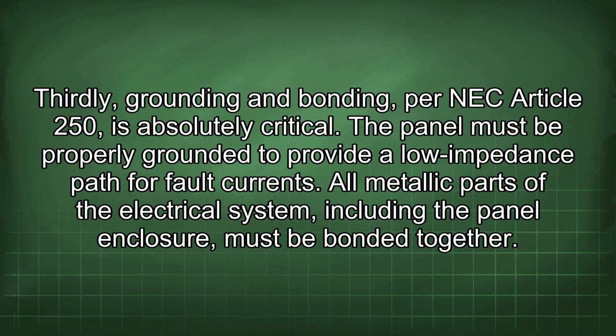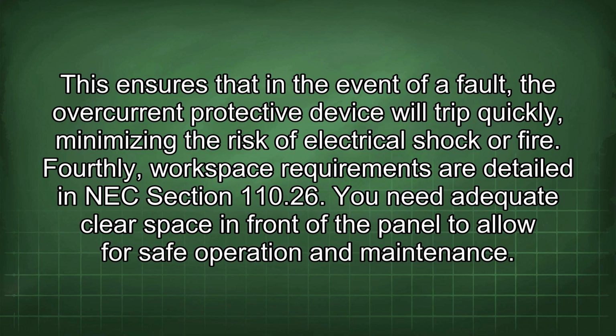Thirdly, grounding and bonding, per NEC Article 250, is absolutely critical. The panel must be properly grounded to provide a low impedance path for fault currents. All metallic parts of the electrical system, including the panel enclosure, must be bonded together. This ensures that in the event of a fault, the overcurrent protective device will trip quickly, minimizing the risk of electrical shock or fire.